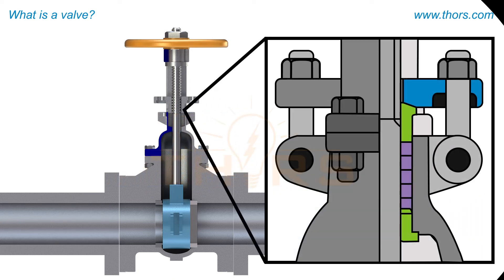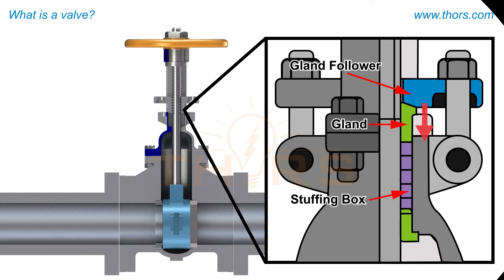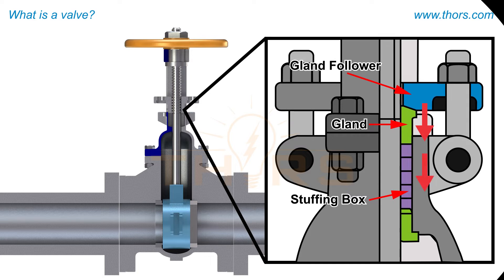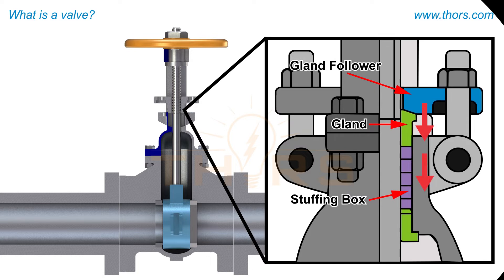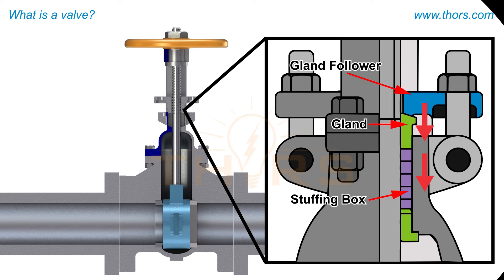A gland packing arrangement consists of a metallic ring called a gland follower, a bushing known as a gland, and a stuffing box. The gland follower and the gland together compress a flexible sealing into the stuffing box to prevent leakage.